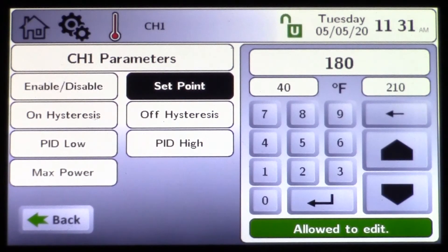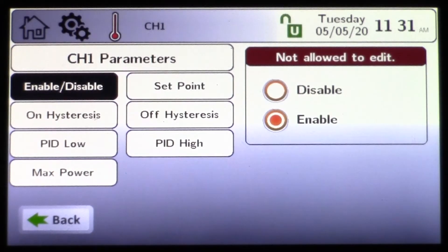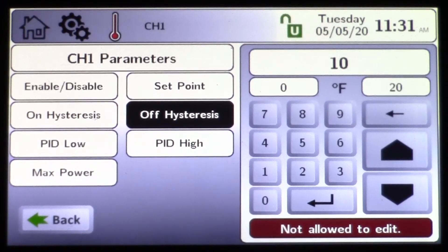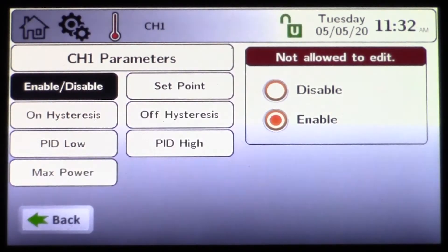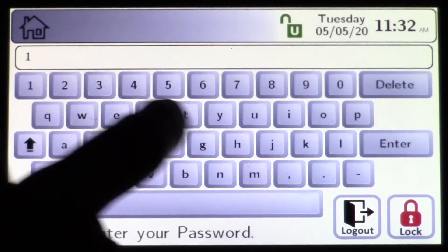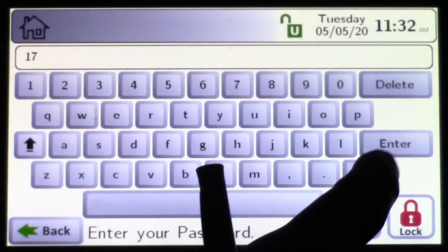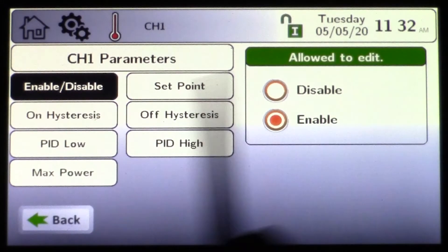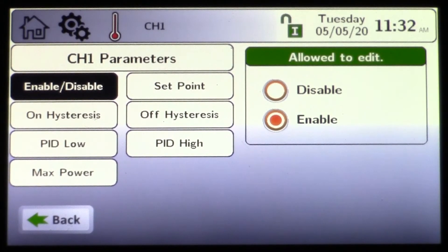You'll see some settings you're not allowed to edit — things like the differential (hysteresis). You need to be in the installer password mode. The installer password is 17. Click the icon and type in 1-7. Click enter and you'll see the letter 'I' for installer appear in the icon, and now you're allowed to edit.